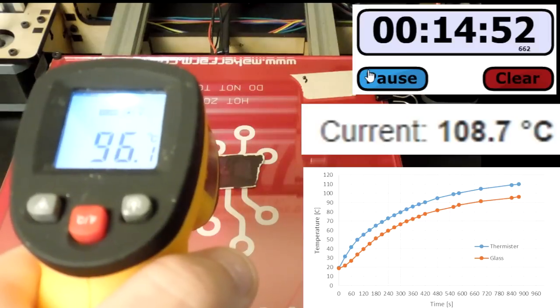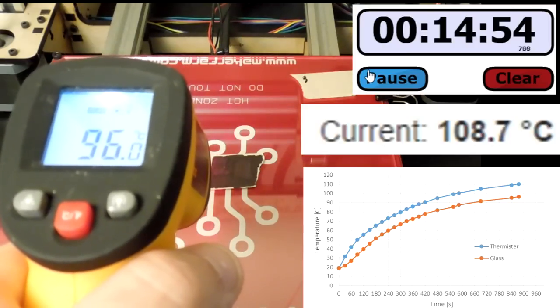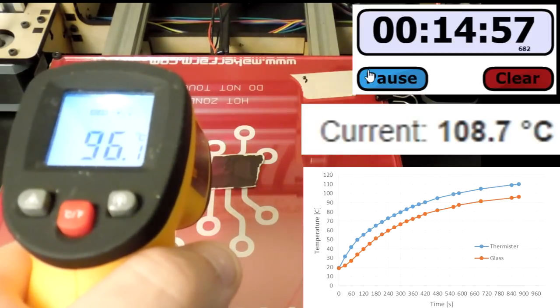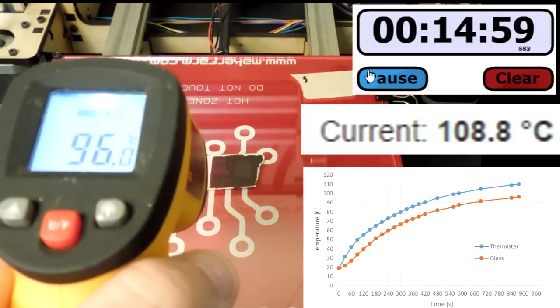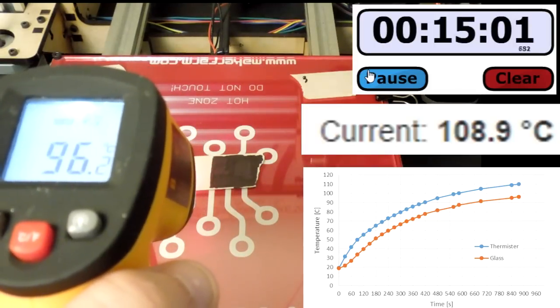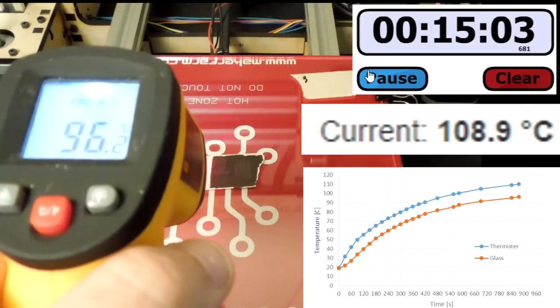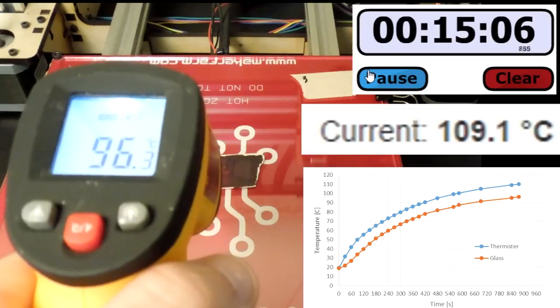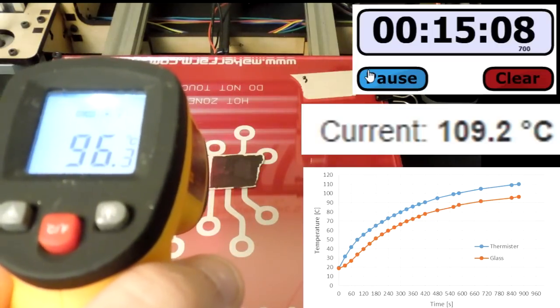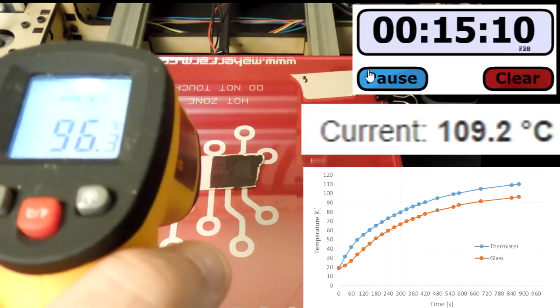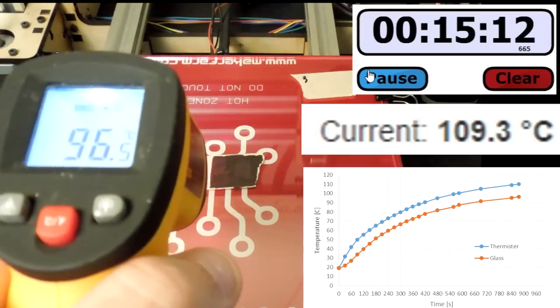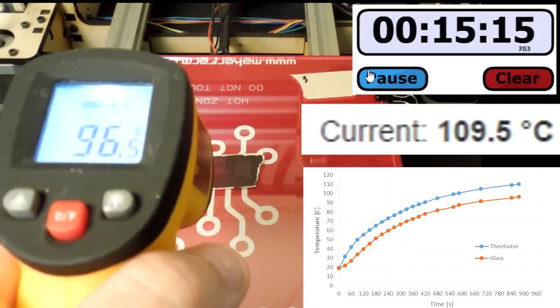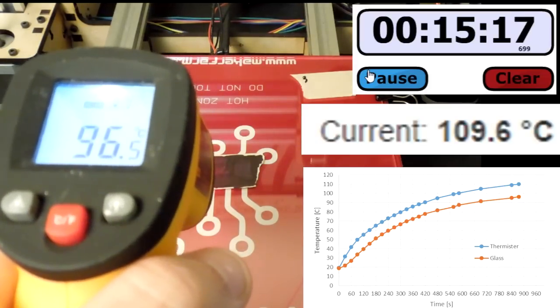The temperature is down to 108.7. Let's see how my PID controller is tuned. It reached 110 and immediately dropped to 108.7, so let's see if it reaches 110 again and see how big that difference is.